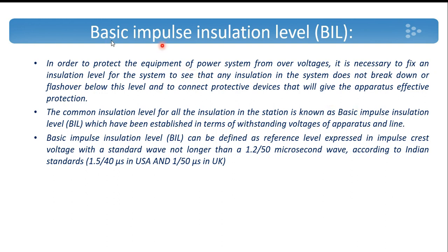The insulation level of a particular station is expressed in terms of Basic Impulse Insulation Level or BIL. Usually, the impulse insulation level of protective devices will be the minimum value. Transformers should have insulation levels 10% more than the protective devices. Transmission lines have more insulation strength than transformers, and bus bars have even more insulation strength than transmission lines. This hierarchy of insulation strength across the power system is called insulation coordination.